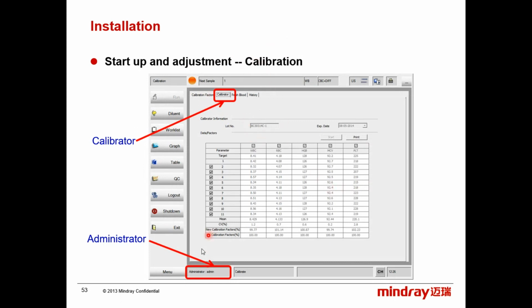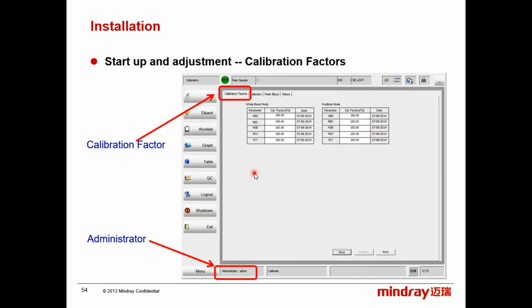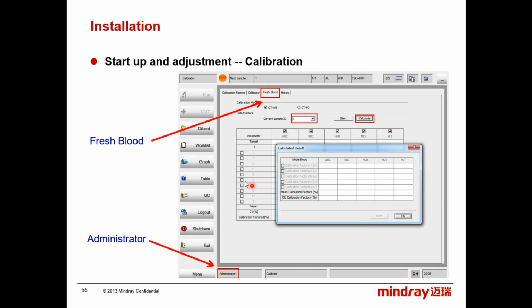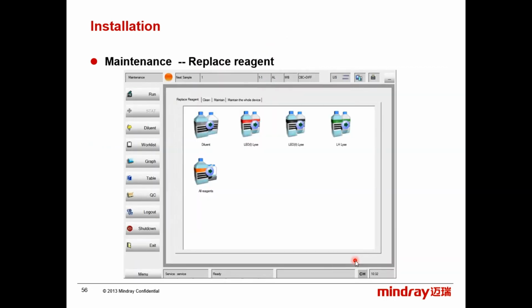Okay, for the calibration, you require administration, because it is normally the responsibility of the operator or of the doctor. So you can use a calibrator, you can use fresh blood, or you can directly calculate your own target factors and then type them in manually. These are the calibration factors for the pre-diluted and for the whole blood. This is for the fresh blood also. Just put the targets and calibrate.